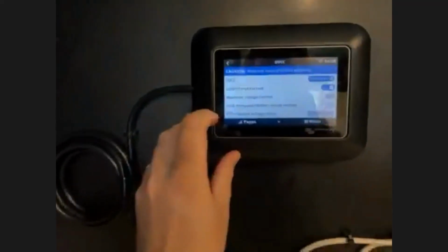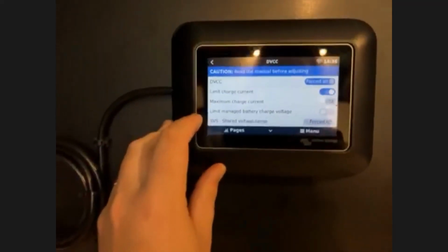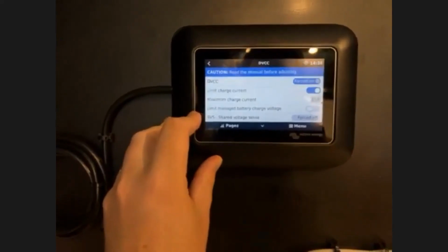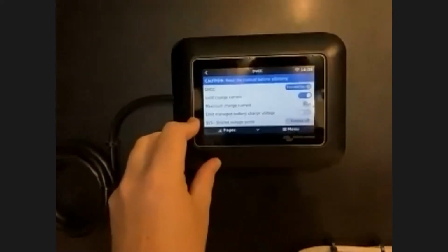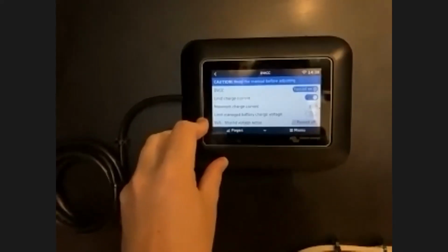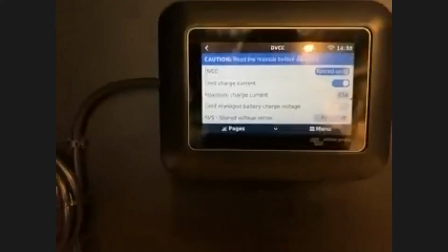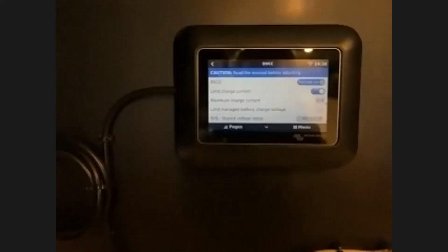You can override some settings here, specifically the limit managed charge voltage. So if, for instance, you want to override those maximum battery voltages or target charge voltages to perhaps correct an imbalance of cells that's happening, or reduce the maximum charge current instead of the battery choosing it, you can override those here. But otherwise, they're set automatically.